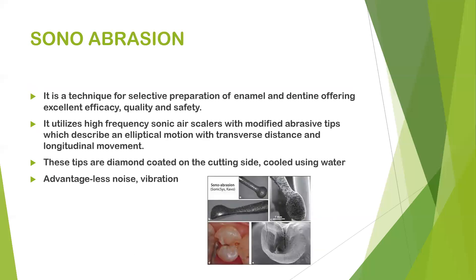Since the 1950s, ultrasonic vibration at high frequency has been recommended for caries lesion removal. Sono-abrasion is a modification of ultrasonic vibration — a technique for selective preparation of enamel and dentin offering excellent efficacy, quality and safety. It utilizes high-frequency sonic air scalers with modified abrasive tips that describe an elliptical motion with transverse and longitudinal movement. These tips are diamond-coated on the cutting side and use water as a coolant, producing less noise and less vibration.